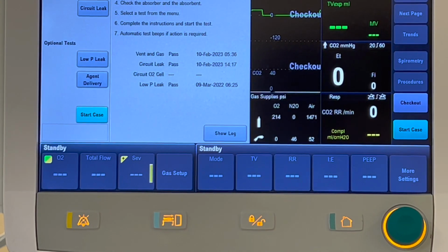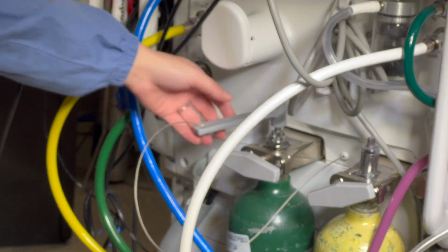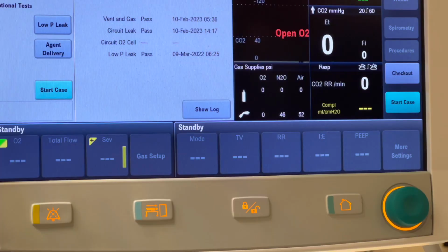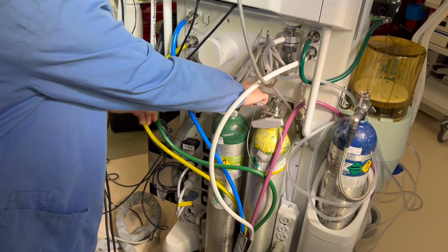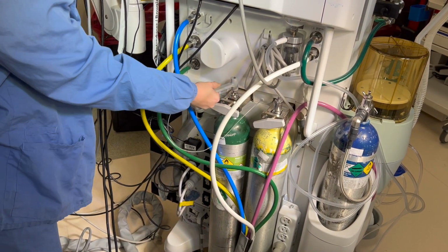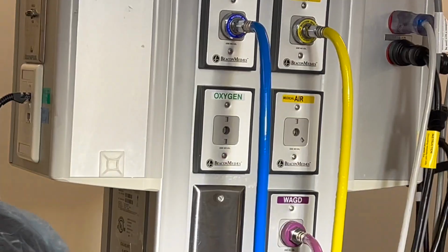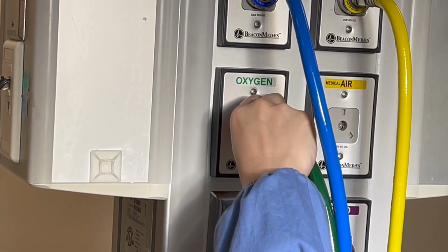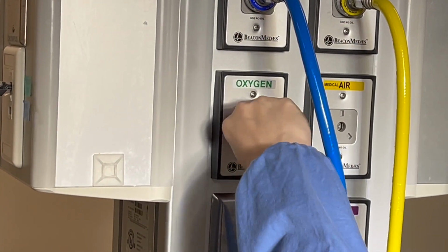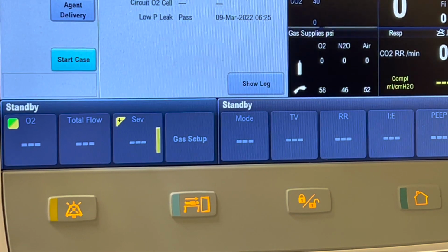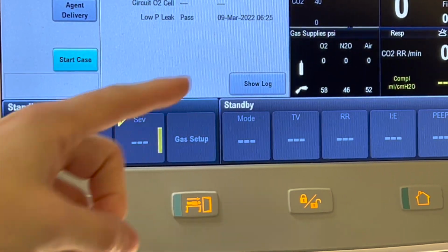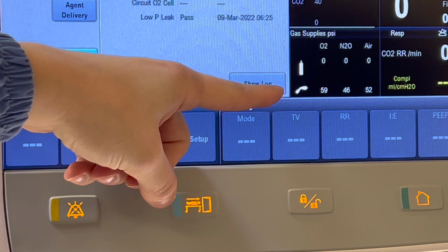Once you do this, you can go back around to the tank on the back of the machine, open the cylinder, then return to the front to see what the current pressure reading is. Once you've got that pressure, you can then go back around and close the tank so that it doesn't drain inadvertently during the case, and then reconnect oxygen as shown. You'll know you've got a firm connection based on visual and tactile feedback. Verify that your pipeline pressures are at or greater than 50 psi, and you'll notice here that our pipeline pressures are located right below our cylinder pressures, which we just discussed.